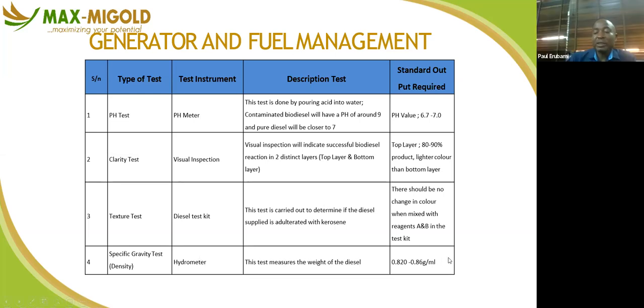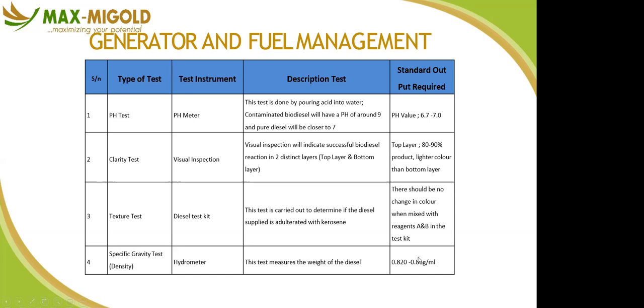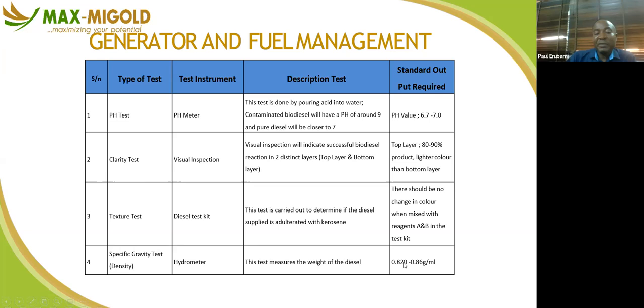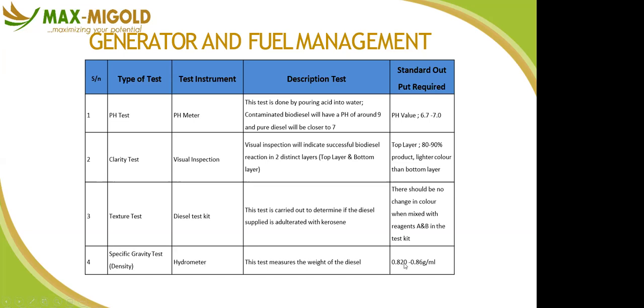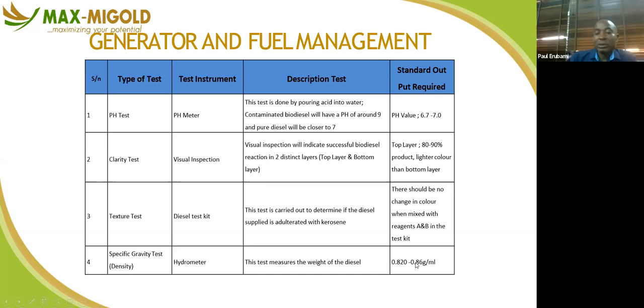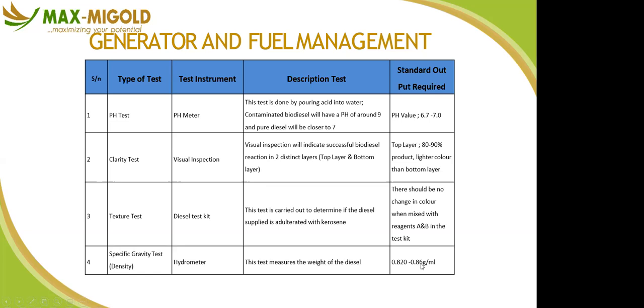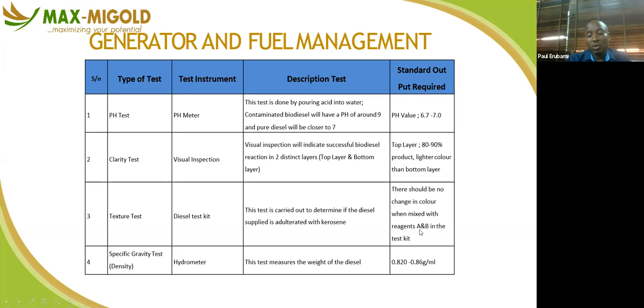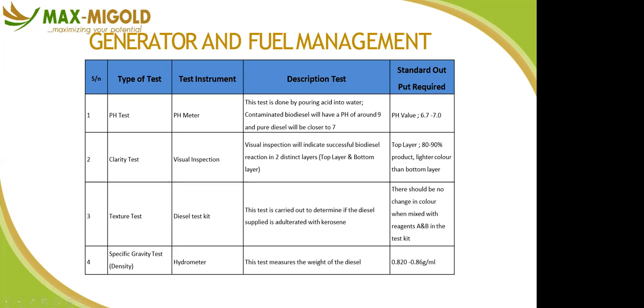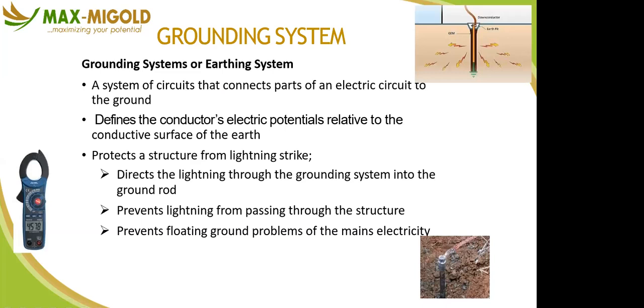So there's a standard in the industry that has been set. This is based on experience that people have had. They have to come to become a standard. So to do specific gravity, it's between 0.820 and 0.86. So if the diesel that you are receiving is far from this range, if it's out of this range, you know that it's not good. So it will help you prevent some damage to your generator.